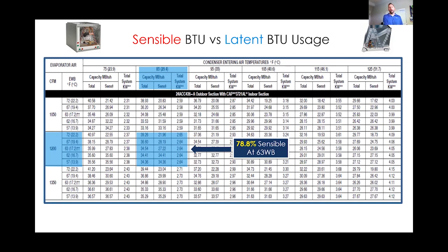An air conditioner is designed to cool the air, not to remove moisture. Now we can use these charts and try to get as close as we can. But when I was looking at this chart and utilizing this in our training platforms, something else just completely jumped out to me. And if I reference back to that entering wet bulb column, if I lower the moisture content in my home, so my entering wet bulb condition is lower at 57 degrees, my air conditioner is 100% sensible, which means every BTU that's coming out of that air conditioner is used to cool my house. That means something else has to dehumidify. And that's when we're going to get into the professional dehumidification systems as the perfect partner in working with your heating and cooling equipment, or excuse me, your cooling equipment, to create this healthy, maintained, and controlled environment.